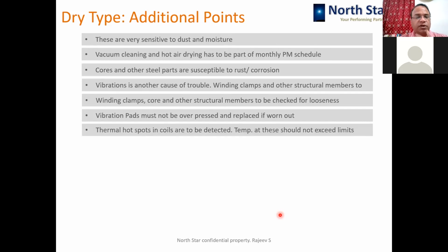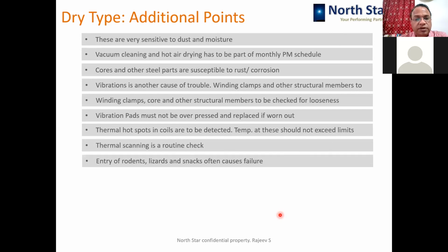Okay, thermal hotspots are present in the cast resin transformer especially, and care should be taken that those limits are not exceeded. So thermal scanning is a very important tool for dry type transformers. In oil filled transformers, thermal scanning has its own limitation because everything is inside the tank. But in dry type transformers, you can actually scan the windings in a very effective way, and you can know that there is a hotspot and you can do something about it before some catastrophic failure happens. So that's why thermal scanning has to be a routine check in dry type transformers.